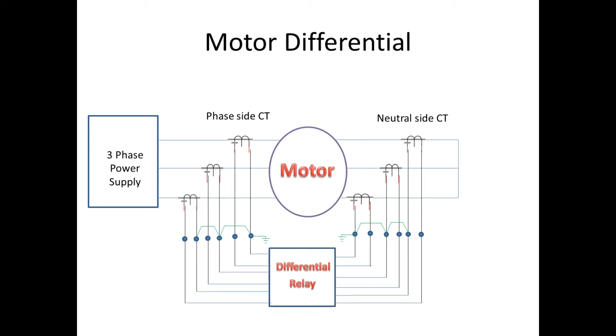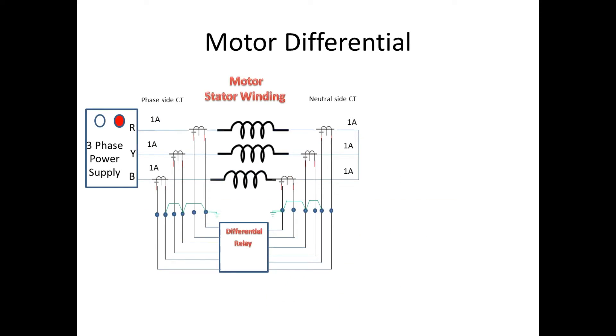Now we can see a small demo for differential protection. When we give supply to the motor, it starts to draw current from the source. Here, the phase side current has to take the path through the neutral side end only. So both CTs will have equal current. Since both have equal current, the relay will not give a trip.